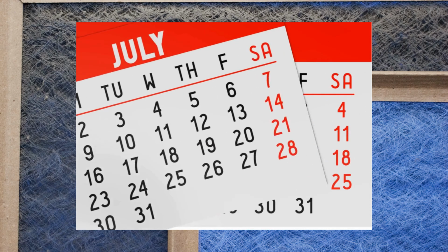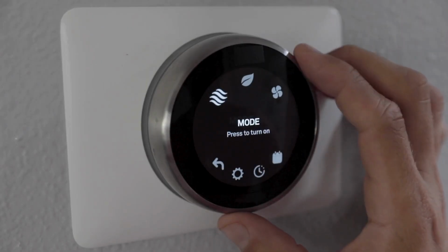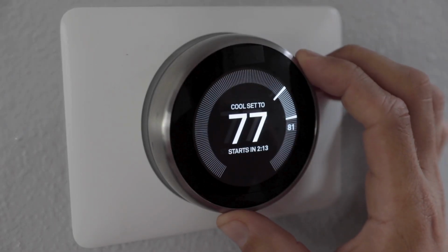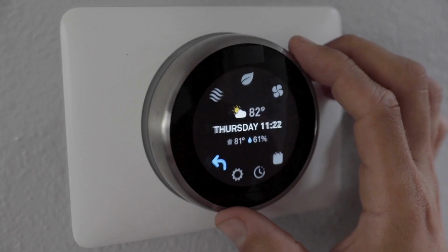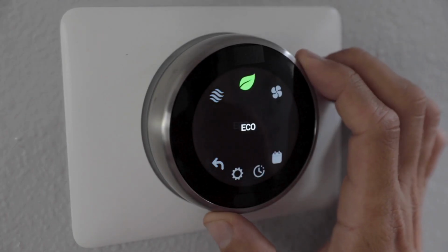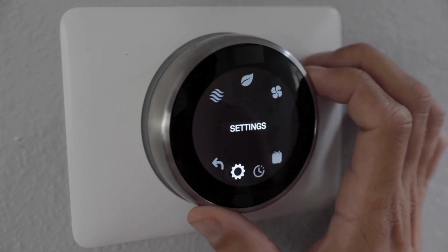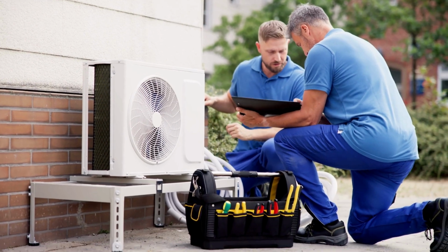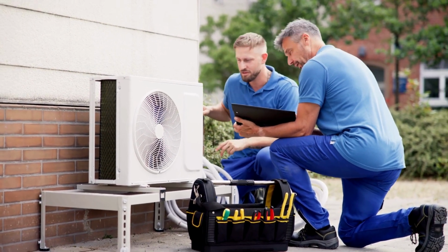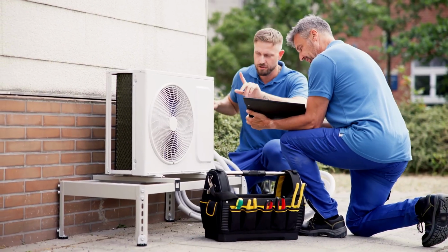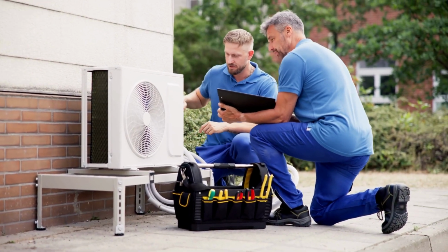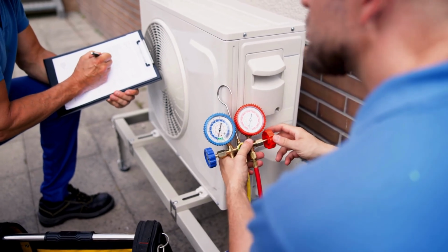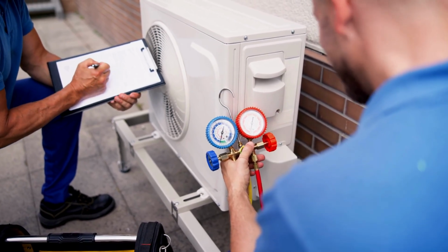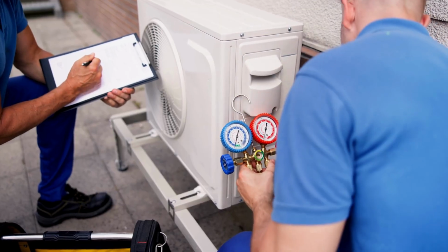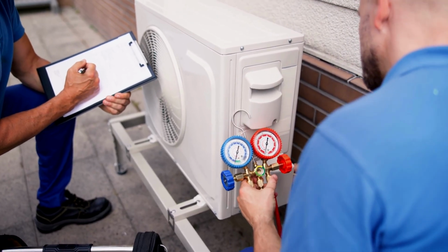Now, if you want a really fine way to know, there actually are some air conditioning systems out there where the thermostats have a sensor on them that can determine if the filter is getting clogged. It'll send you a little signal, and that's kind of cool. But they also make devices that you can actually put in the filter, like I was talking about the manometer, and you can determine what the pressure drop is across the filter. You can get your HVAC company to do that, or you can Google it and find out the process. Maybe it's starting clean at a 0.1 or a 0.2, and when the filter gets to a 0.25, okay, now that's when I'm going to change it.